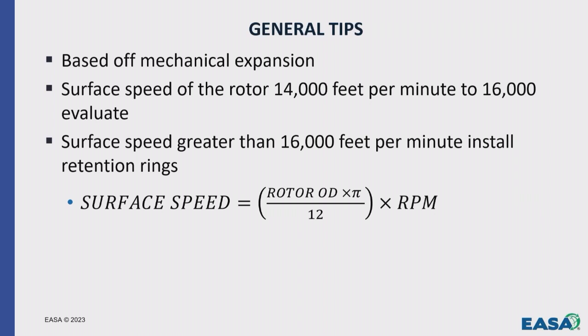Now anything over 16,000, I go ahead and put them on. I know it's going to be safe, I know it'll do what it's supposed to do, but the gray area is always 14,000 to 16,000 feet per minute, and that's when you have to evaluate. If you're not sure, if you're repairing something and one's broken, just put it on. It's better to be safe than sorry. But usually between 14 and 16, we'll do a little more advanced calculations. Look at the duty cycle, how many times it starts, and then we'll make an evaluation if it needs to be installed or not.